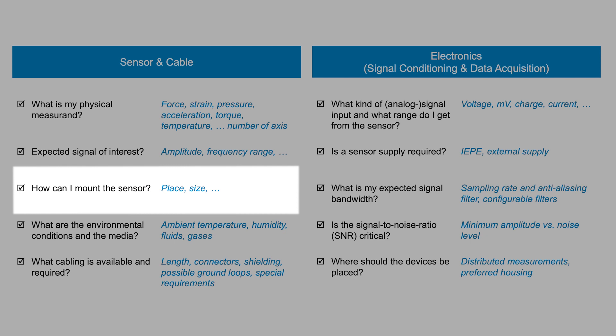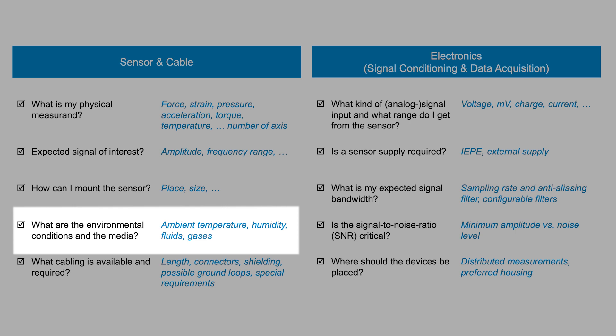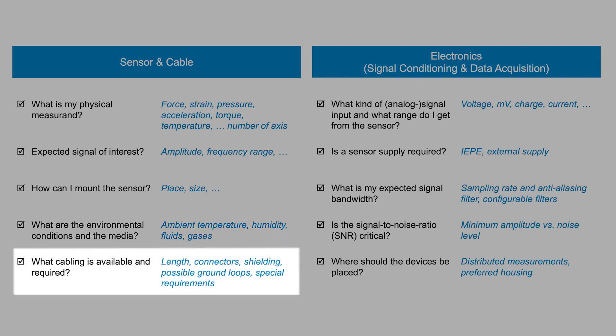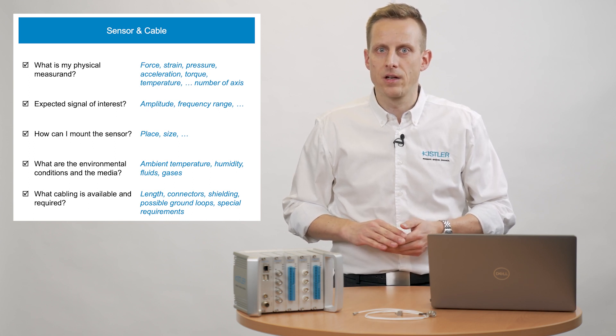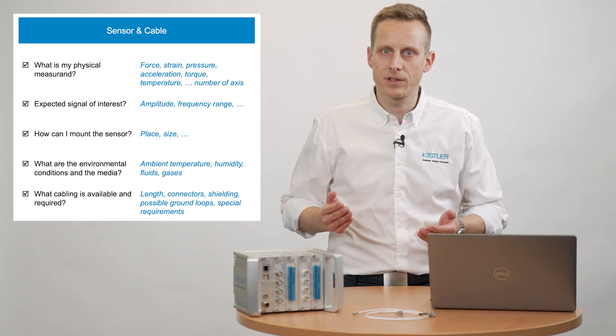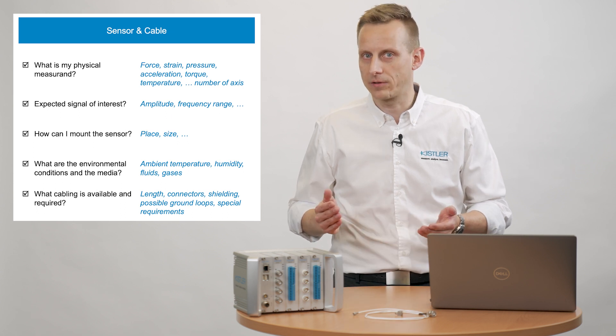Mounting — this is very dependent on the measurement. For example, with acceleration: how can I mount the sensor? Can I bolt it, or should it be bonded with wax? Then about ambient conditions: what is the expected temperature range? Are there fluids or gases which are potentially harmful for the sensor? Cabling may be very important, as mentioned before — not only the length and connectors, but also electromagnetic influences. Shielded cables or twisted pair for differential signals? Or the potential for ground loops?